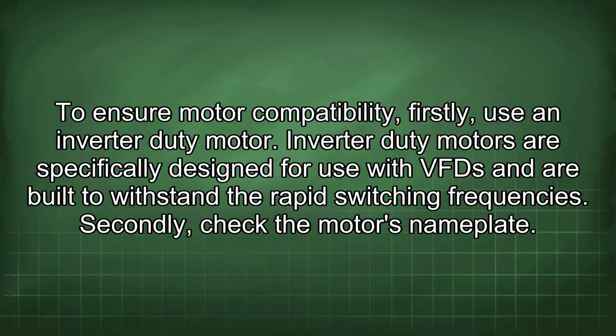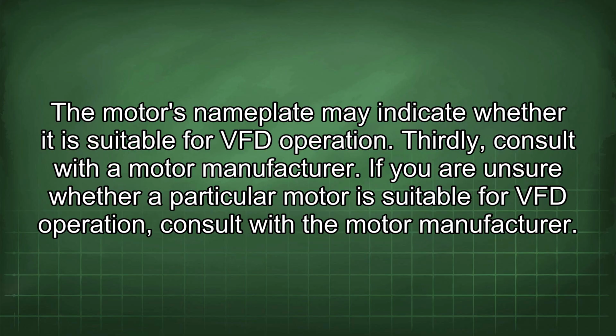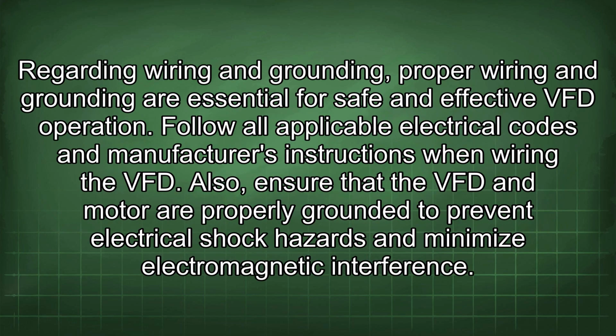Secondly, check the motor's nameplate. The motor's nameplate may indicate whether it is suitable for VFD operation. Thirdly, consult with a motor manufacturer. If you are unsure whether a particular motor is suitable for VFD operation, consult with a motor manufacturer. Regarding wiring and grounding, proper wiring and grounding are essential for safe and effective VFD operation. Follow all applicable electrical codes and manufacturer's instructions when wiring the VFD. Also, ensure that the VFD and motor are properly grounded to prevent electrical shock hazards and minimize electromagnetic interference.